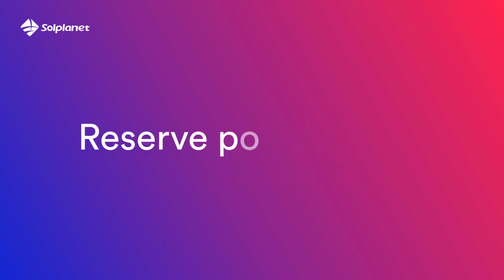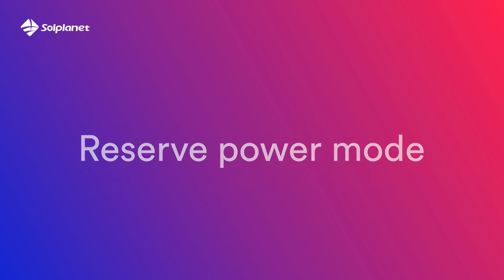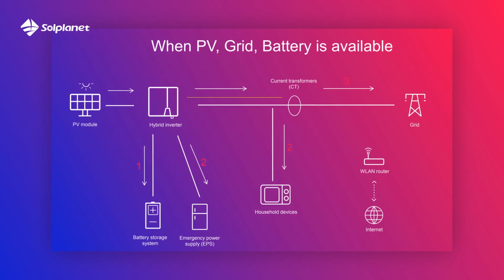Work modes, reserve power mode. When PV, grid and battery are available, solar energy will charge the battery as first priority. If solar energy is excess, the excess power will supply the load. If there is still some extra energy, then the excess power will feed to the grid.